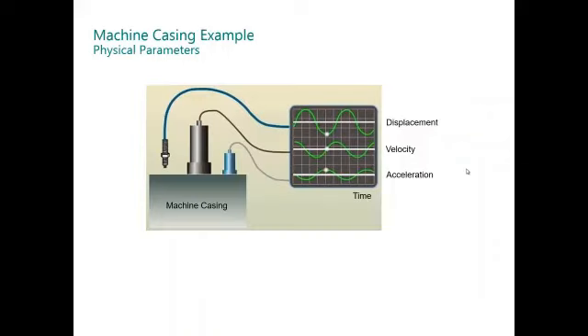In this example, it represents three measurements of the machine case: one for displacement, the second is velocity, and the third is acceleration. Reviewing the top and the bottom, you can observe that these are opposite sine waves. That means when the displacement is at the maximum positive, the acceleration is maximum negative, and the velocity is displaced 90 degrees apart between displacement and acceleration.